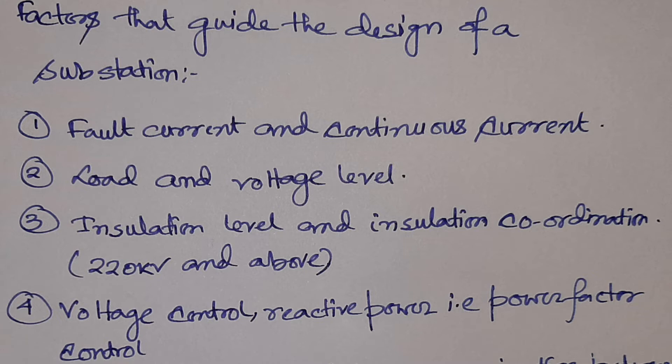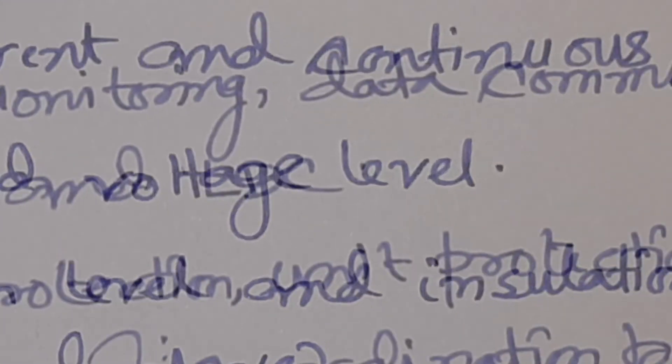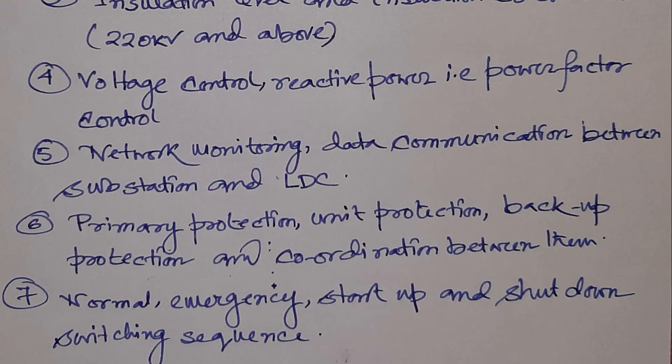Then there comes voltage control and reactive power control. Reactive power control is basically power factor control. Both voltage control and reactive power control can be done by controlling power factor — that is, adding capacitors to the system. A synchronous condenser is also one method but it is an older approach and due to its complexity it is not generally used, so power factor correcting capacitors are most often used.